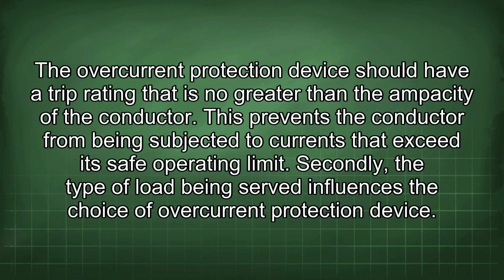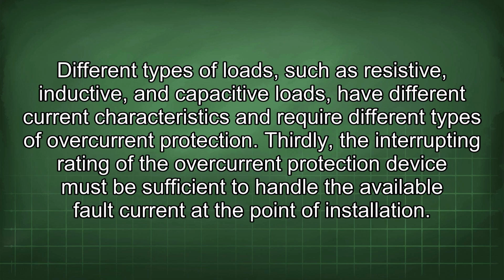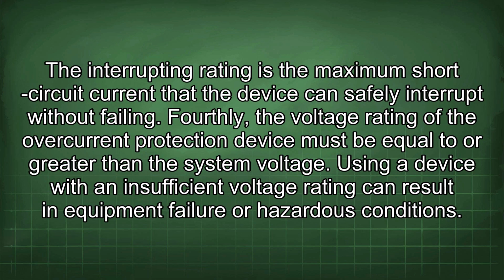Secondly, the type of load being served influences the choice of overcurrent protection device. Different types of loads, such as resistive, inductive, and capacitive loads, have different current characteristics and require different types of overcurrent protection. Thirdly, the interrupting rating of the overcurrent protection device must be sufficient to handle the available fault current at the point of installation. The interrupting rating is the maximum short-circuit current that the device can safely interrupt without failing. Fourthly, the voltage rating of the overcurrent protection device must be equal to or greater than the system voltage. Using a device with an insufficient voltage rating can result in equipment failure or hazardous conditions.